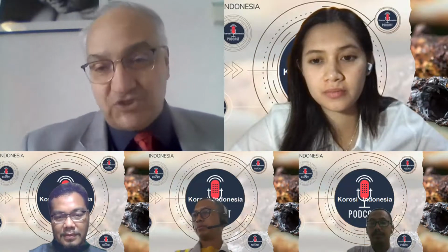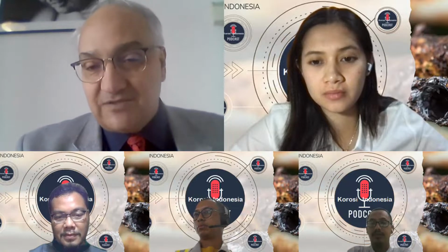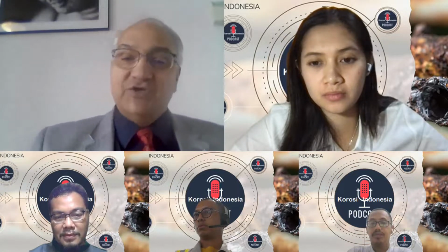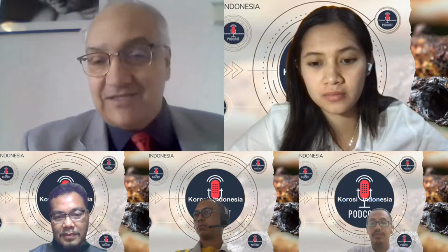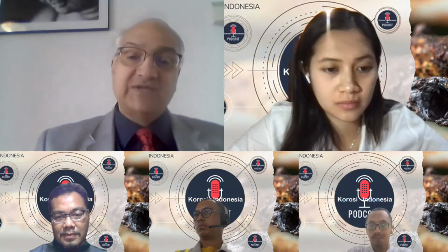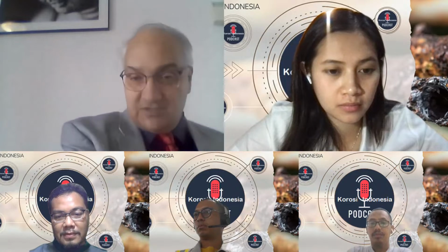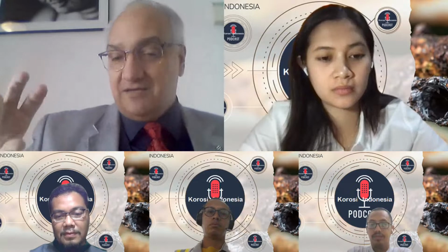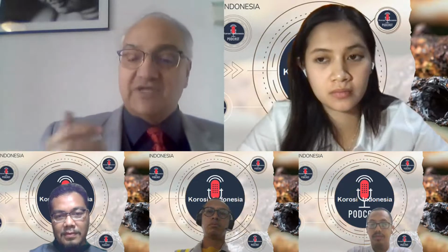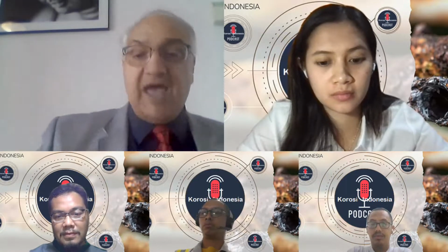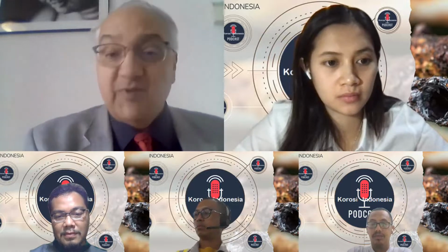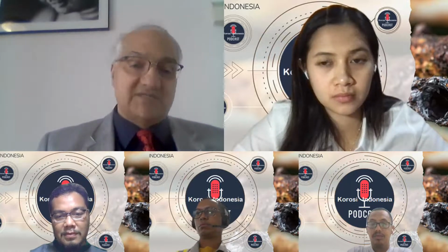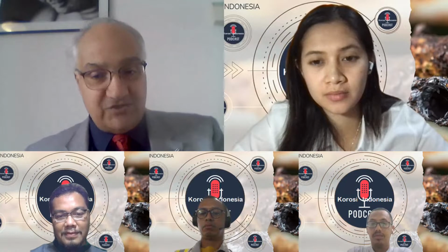This shows that the oxygen scavenger had been administered unwisely. You had sometimes added too much, so that the environment had become deoxygenated and you got magnetite, and sometimes very little oxygen scavenger had been added, so that you got a lot of oxygen and hematite. So it is not always the case that microbial corrosion may come and strike.